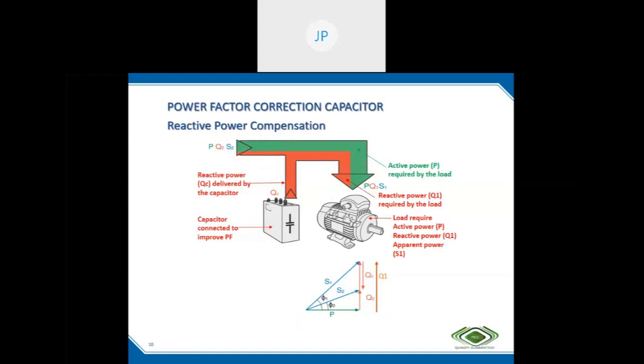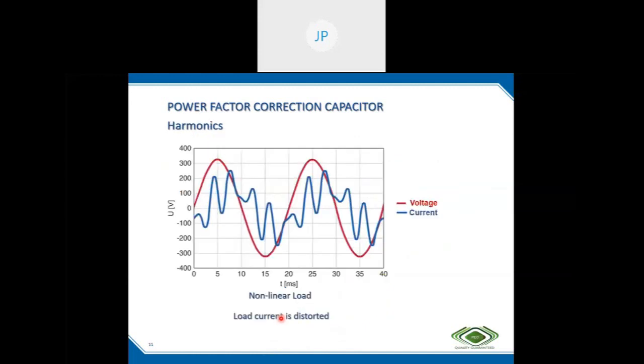This you can also see from the vector diagram. Q1 is the required reactive power, QC is the delivered, and only the difference is drawn from the source. So the power factor improves from cos phi1 to cos phi2. Now we can consider the non-linear load.